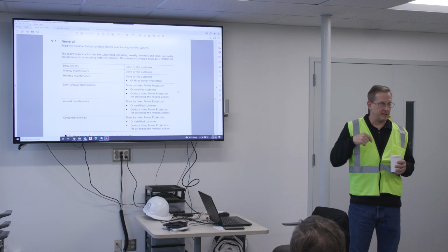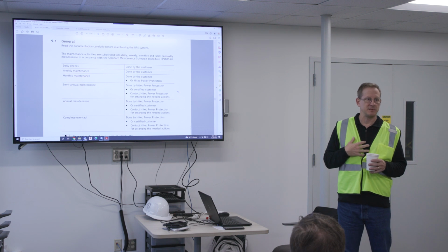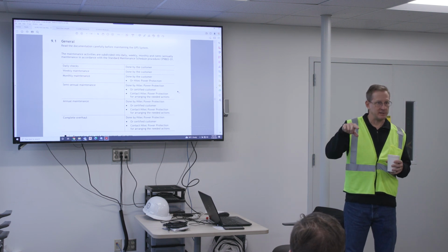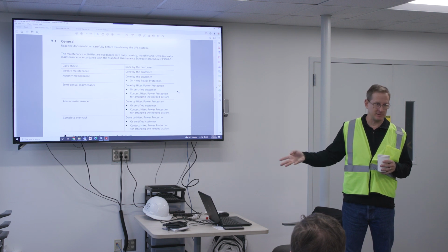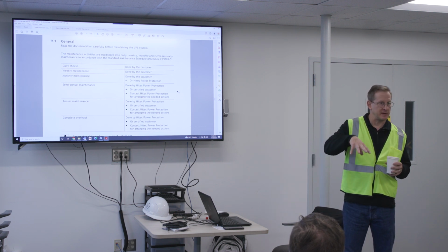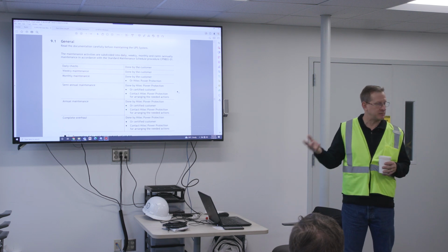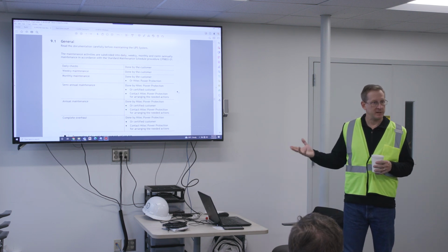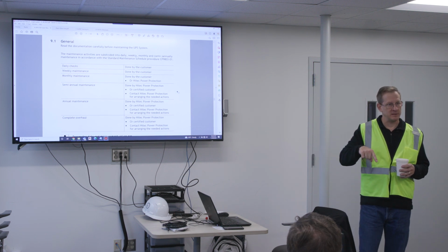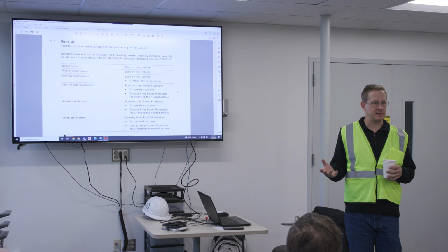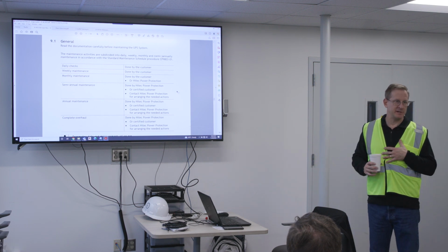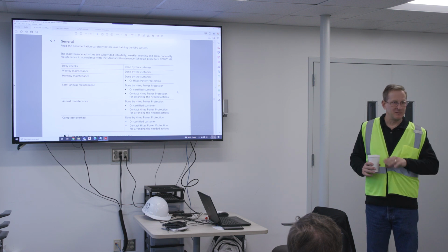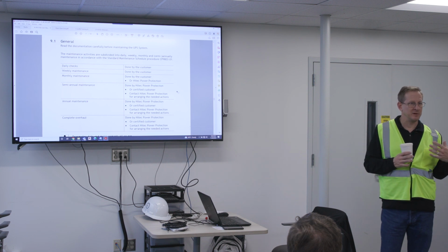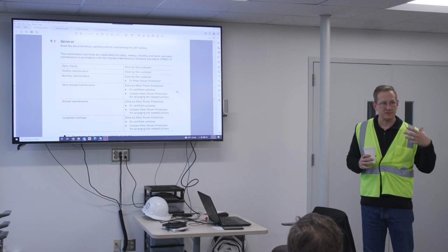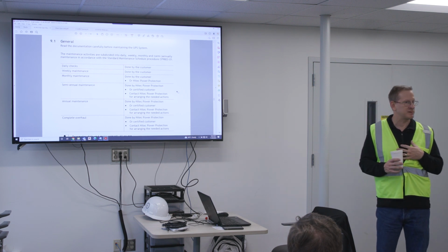Even though you may have a contract with us for maintenance of the system, we may not be the ones coming to actually maintenance the switchgear. We'll contract that out to another party to do things like switchgear or diesel maintenance. We'll contract with Cummins to come here and do that, and we'll contract with Eaton, for example, to come service the breakers in the switchgear. So that's how we handle that. It may not be our technicians getting into the switchgear or the diesel, but we'll contract that out. We'll handle the things that are high-tech in nature, like our own systems, our flywheels, our controls. We'll obviously handle all that with our own service members.